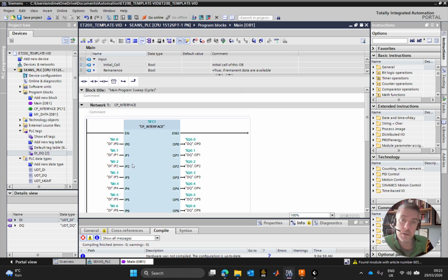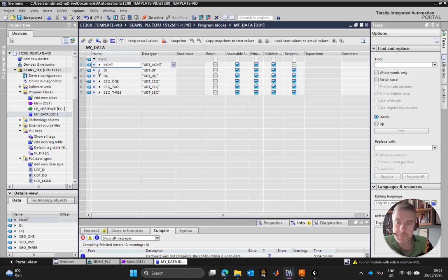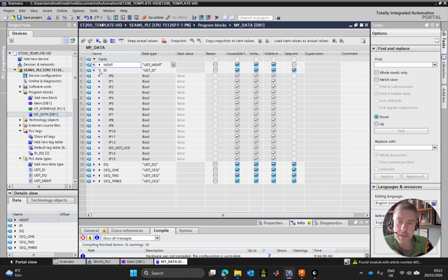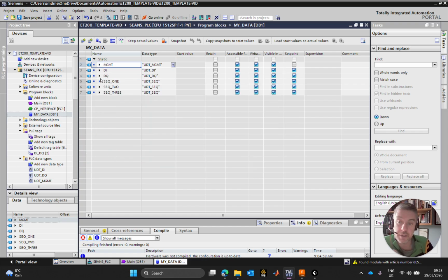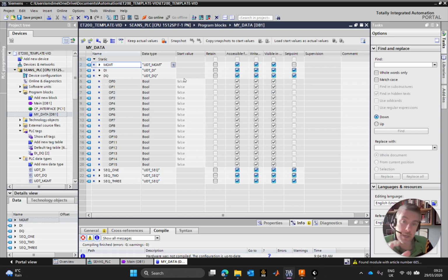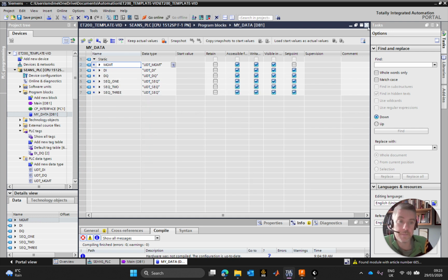Specifically on the output. So the output is going to go high if the data input goes high. But what I could potentially do in OPC is that if I run online, I could force that to go high. I don't know those force tables for these things, but to get onto a force table, we need to be looking around PLC. But this now data block, because OPC UA is enabled, I will be able to access this data block from anywhere once I have the IP address, the port number, and indeed once this block is enabled on the OPC.